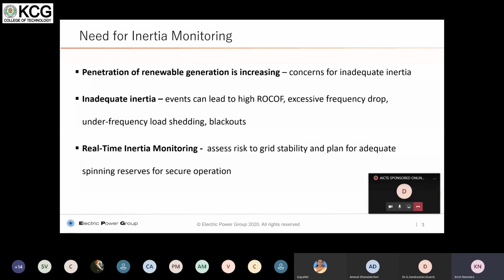Why I'm telling you this is that the electronics used in the wind, the solar and the battery backup systems do not provide any inertia to the system. Solar absolutely does not have any rotational parts, so it cannot store energy or give back the energy. Let's take the battery backup system. Battery backup systems are also static in nature. They do not have any moving parts. Hence they cannot support inertia in the system.